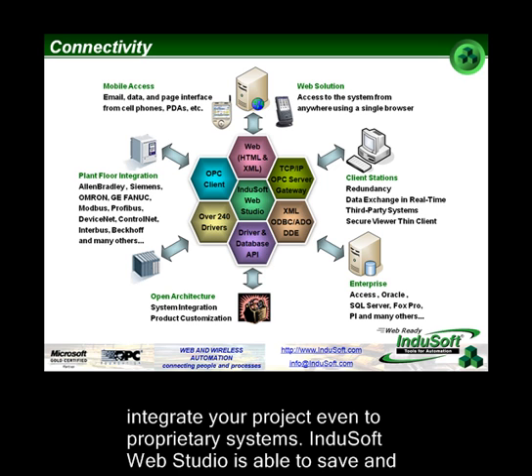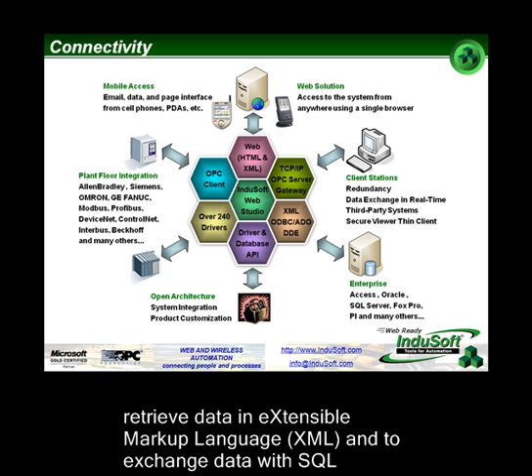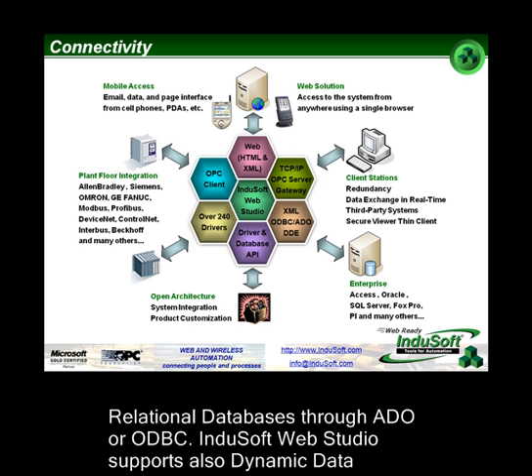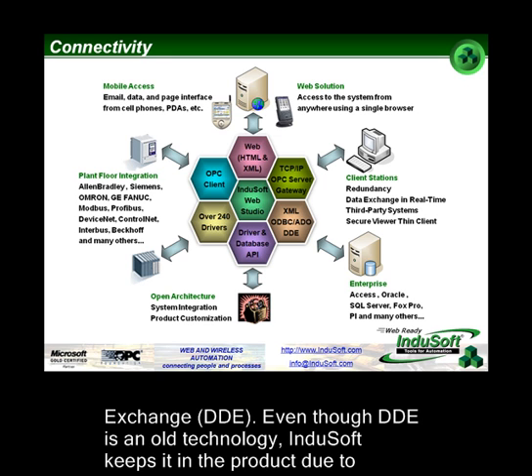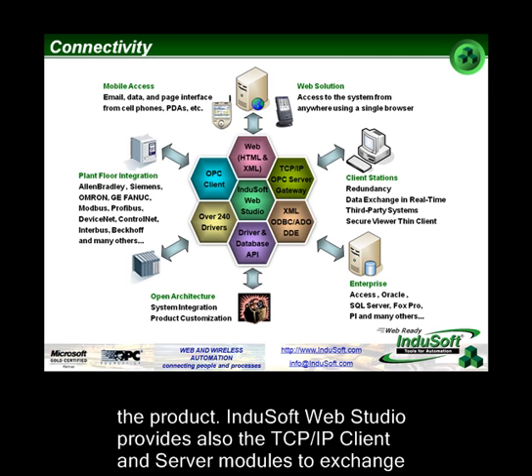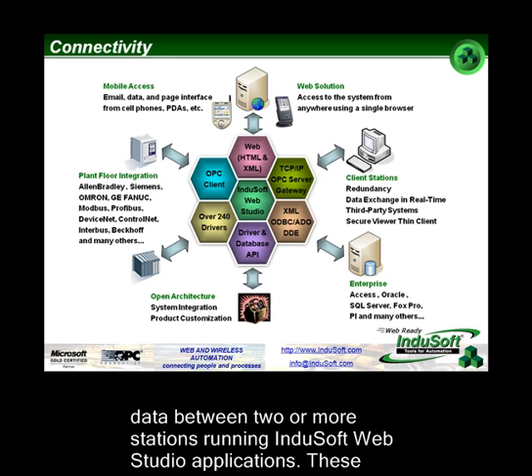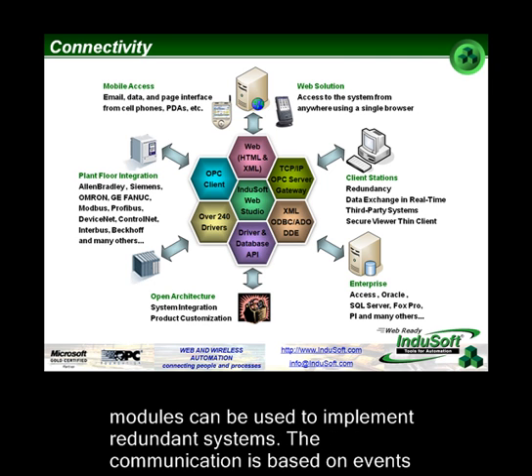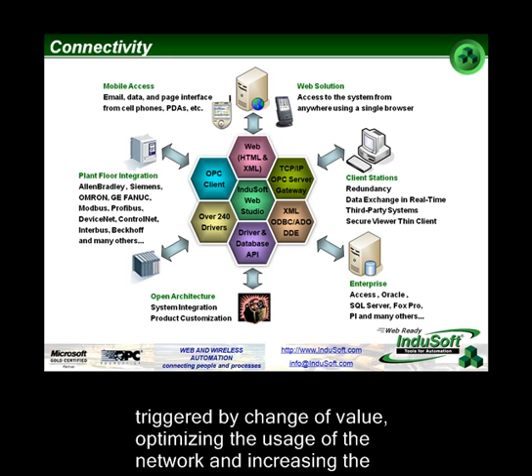InduSoft Web Studio is able to save and retrieve data in extensible markup language and exchange data with SQL relational databases through ADO or ODBC. InduSoft Web Studio also supports dynamic data exchange. InduSoft Web Studio provides TCP/IP client and server modules to exchange data between two or more stations running InduSoft Web Studio applications; these modules can be used to implement redundant systems. The communication is based on events triggered by change of value, optimizing network usage and increasing performance.